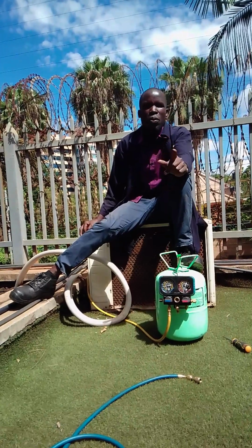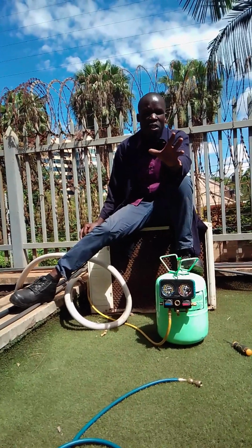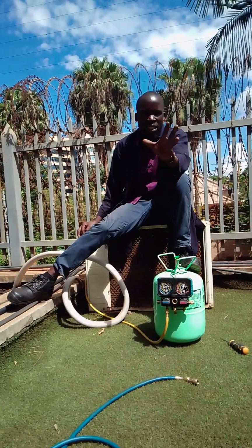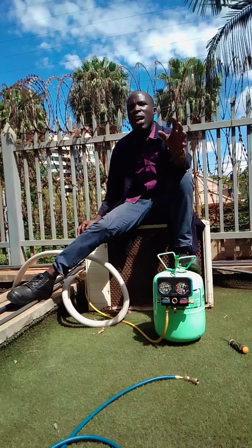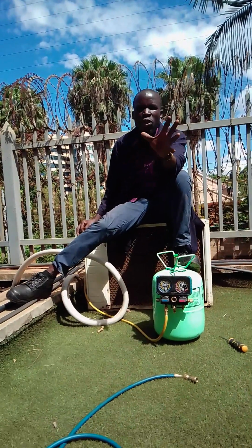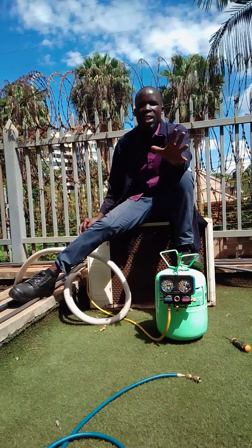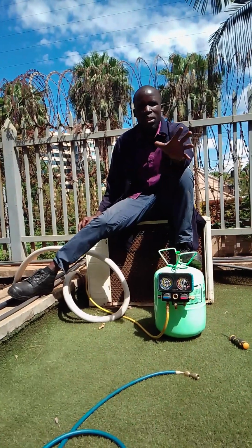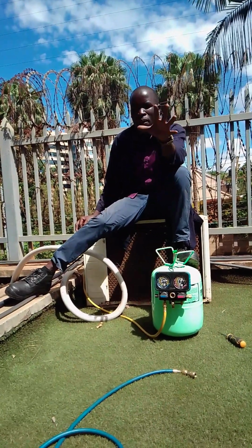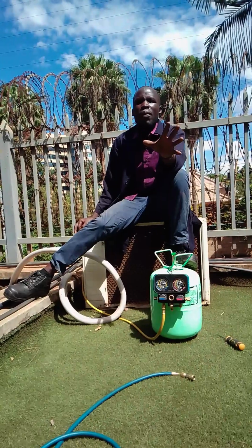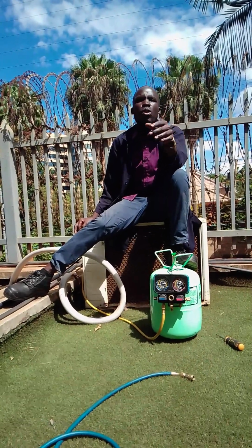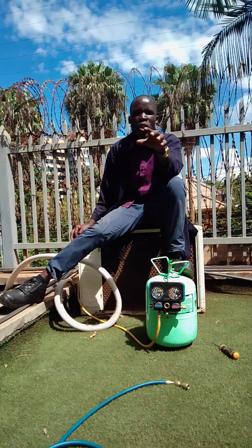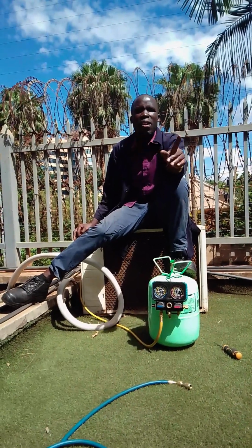One, there could be debris in the condenser, affecting the heat exchange. Therefore, you need to analyze whether there is debris or the condenser fins are very dirty, stopping the heat exchange from taking place. Sometimes the extraction fan is not running, so you have to analyze the motor of the extraction fan.